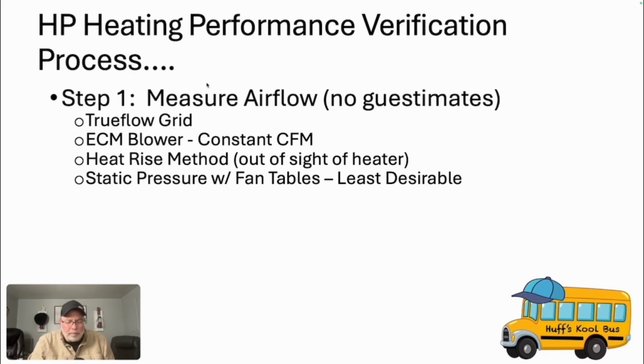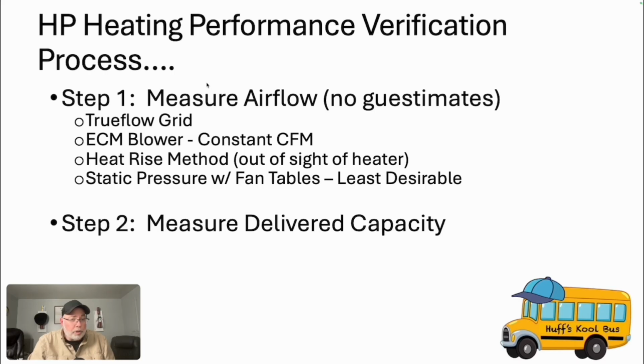However, when you've got a really turbulent duct system, I have seen, especially with short supply plenums with multiple taps coming out, where we don't have a good, straight section for laminar flow of air, that turbulence will cause issues in that airstream. You may put that static probe in the center of that supply plenum and then move it 2 inches to the left or 2 inches to the right and get a totally different reading. And so that's why we don't like to use this for measuring airflow for this performance. So step one has to be measuring airflow. Step two, we measure the delivered capacity.